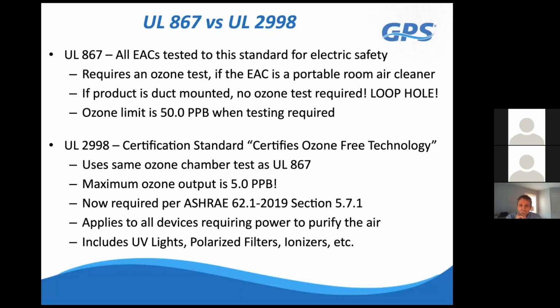And so with 2998 certification, you use the same chamber as 867, still measuring 2 inches away, but it doesn't matter if the products are duct mounted or portable room air cleaners, they now have to be certified to produce no more than 5 parts per billion. So we're 10 times lower in ozone levels, which is really even lower than background levels outdoors if you were to go outside and measure ozone. And so that does apply to UV lights, polarized filters, ionization systems. And so they're all supposed to have this 2998 certification to comply with the latest edition of ASHRAE 62, section 5.7.1. And so I'm saying all this just to kind of get you educated on the UL standards.